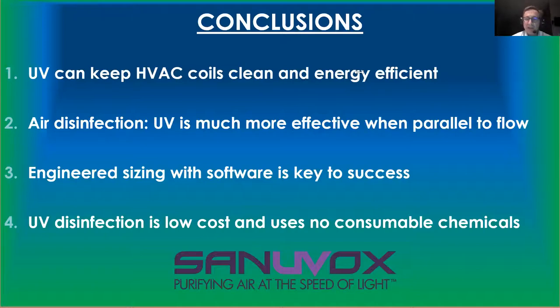If you put them downstream, you will see a lot more water. You will see cold air hitting the lamp. What we do when we have that situation, we put more lamps. We have a correction factor in our program. And if you choose downstream in the calculation sizing software, it will put more lamps to do the same installation. You will get a depreciation for fouling and a depreciation for lamp cooling. So yes, it makes a difference.